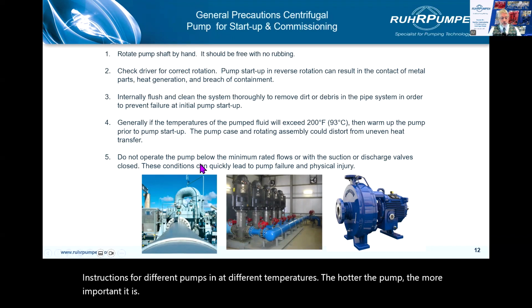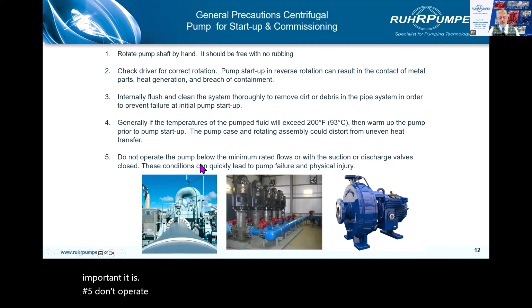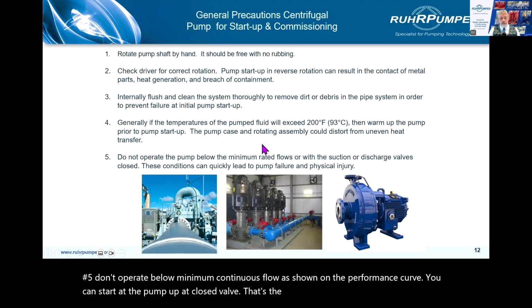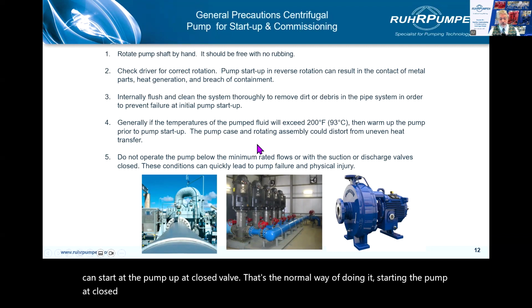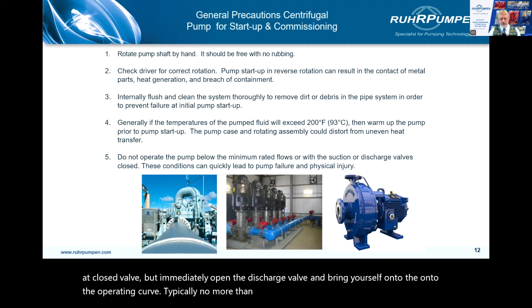Number 5, don't operate below minimum continuous flow, as shown on the performance curve. You can start the pump up at closed valve. That's the normal way of doing it, starting the pump at closed valve, but immediately open the discharge valve and bring yourself onto the operating curve. Typically no more than 15 or 20 seconds at shut-off.